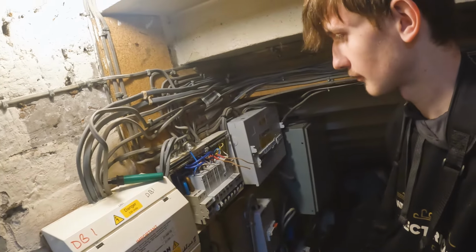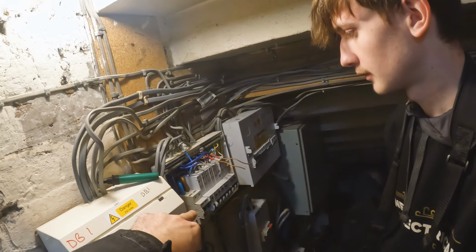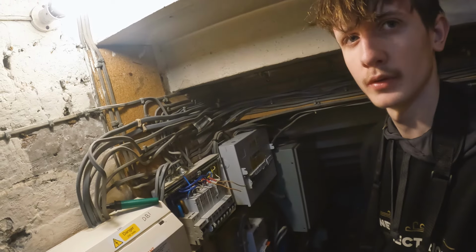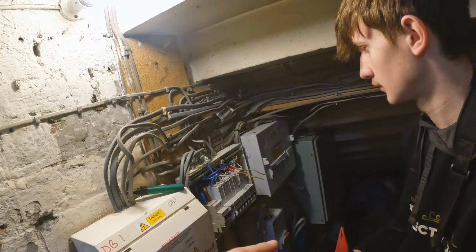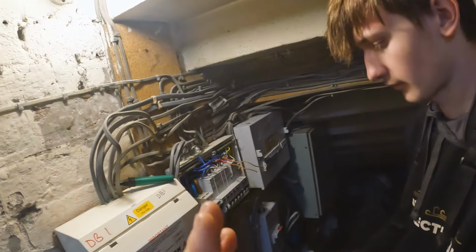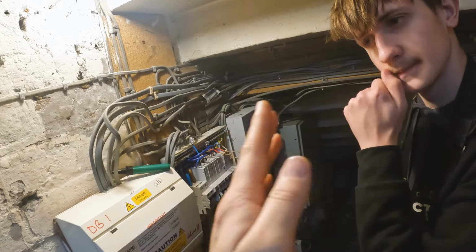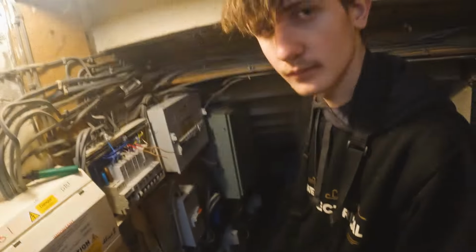And then what else does this RCBO do? Earth leakage. So earth leakage, okay. And then what's the rating of this one? 30 milliamps. So anything over that it'll cause it to trip. So if you've got anything in this circuit that's line to earth or neutral to earth, basically the line goes out, goes through a solenoid and comes back. If it goes anywhere else, which is the leakage, and it's more than 30 milliamps, it's going to trip. So there could be a wire in a fitting, some fitting that's on its way out, creating more than 30 milliamps leakage. So those are things to be looking at.